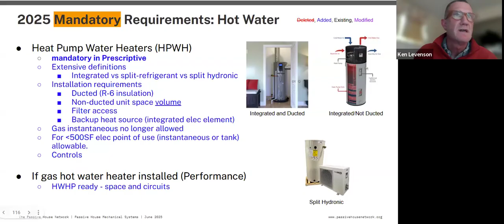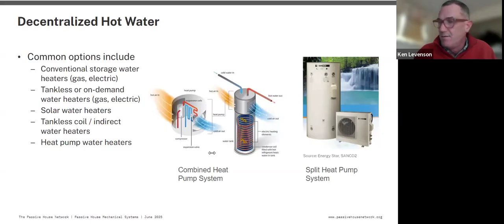So it's not so much a Passive House thing for much of the mechanicals, it's just getting it to work as it would for any building. I think Passive House is just a bit more sensitive, since the heat pump water heater is removing hot air from the space and cooling it, and because the space is quieter, you're more sensitive to the noise of the system. So it makes you want to plan for that more effectively.